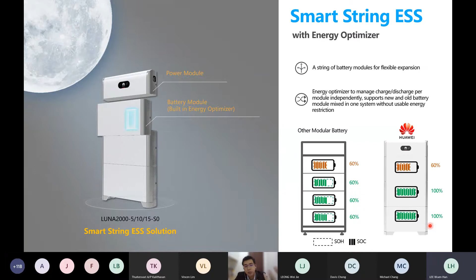So when you install a new battery, in this case 3 battery modules, what happens is that when you charge it, it will not go to 100% even though the SOH is 100%. It's actually kept at the old battery SOH of 60%. Whereas for the Huawei solution, like I mentioned just now, we have our very own built-in energy optimizer. So even though the old battery SOH is 60%, when you couple it with the new battery, it can actually charge to 100%. So the performance of the battery is much better, as it should be.